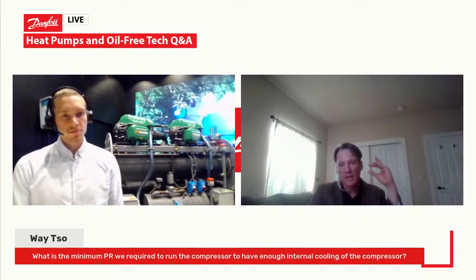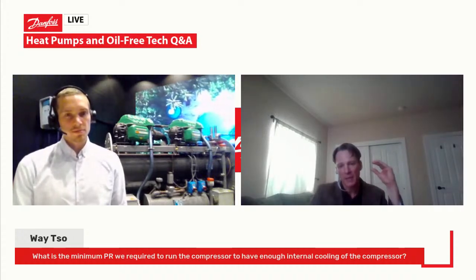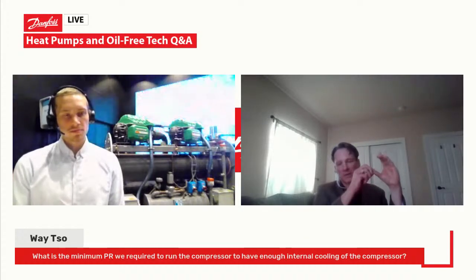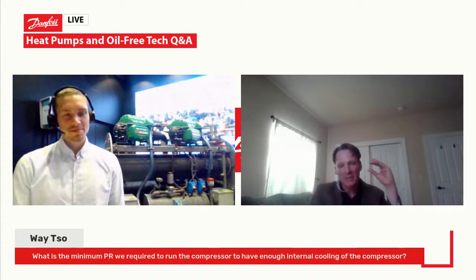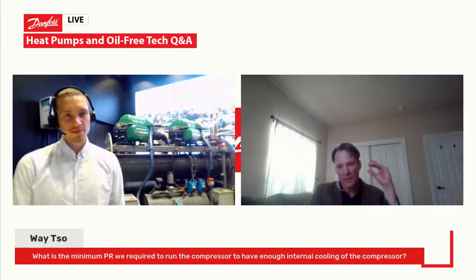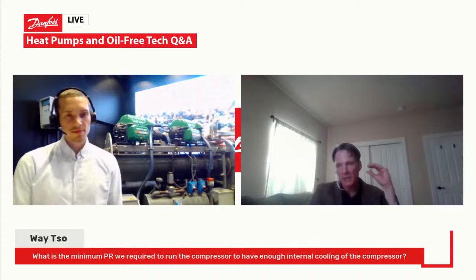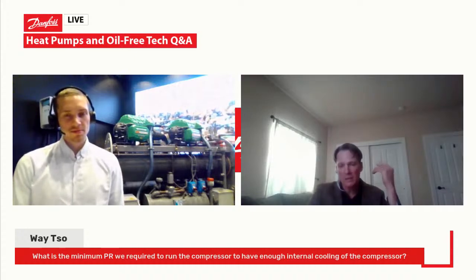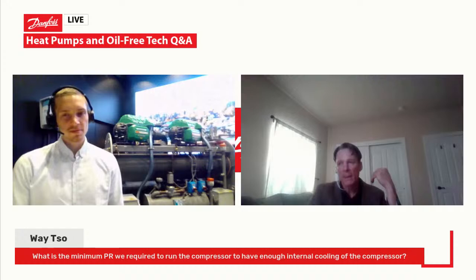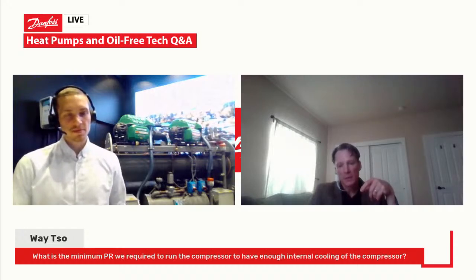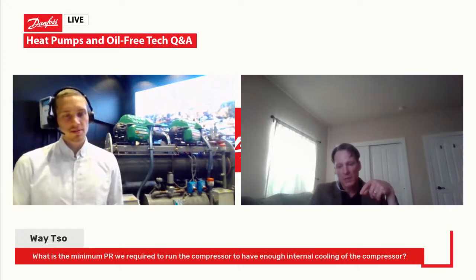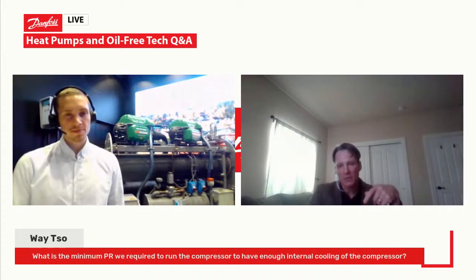So you can lower down that differential from the heat rejection on the high side to the cooling on the low side. You can lower down that pinch even more, and so therefore operate at much lower differential and much more efficiently. And so that's a longer answer to your question: with the low lift solution, which enables the cooling or a pump assist cooling back to the power electronics, you can operate as low as a 1, or the equivalent discharge temperature to suction temperature pressure ratio.